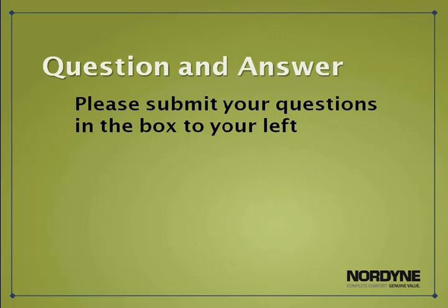Mike is asking with National Sales, after a call for cooling on a 90-degree day, what step will the unit start on? Again, it's going to be based on the Y1, Y2 input. If you are restarting the cycle with a Y2, you're going to start at that C4. If you're only putting in a Y1 input, that's determined by the prior run cycle and length of time that it ran, and it will determine which one of the first three stages the unit will run at. That's all built into the software, and it's based on runtime and temperature outside. So I guess on a 90-degree day, if you only have a Y1 input, you're most likely going to go up to stage 3 of cooling.